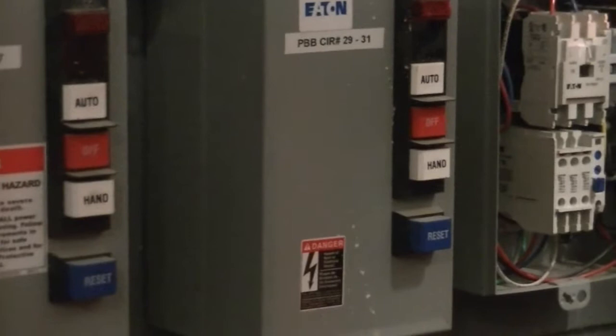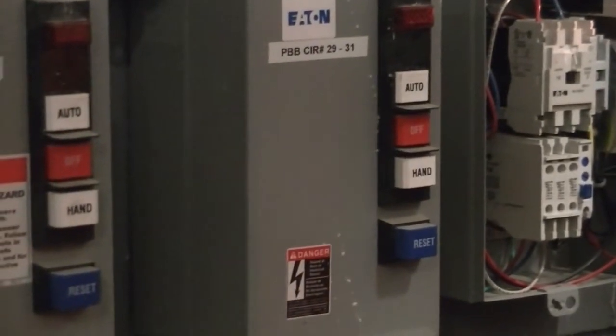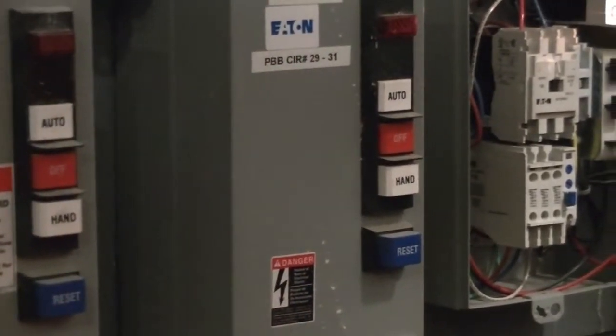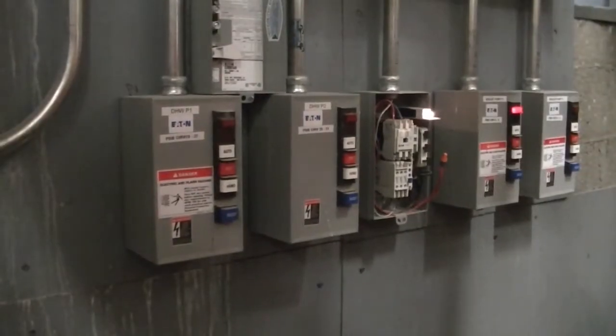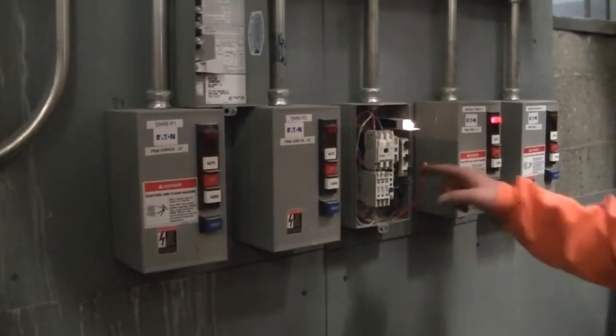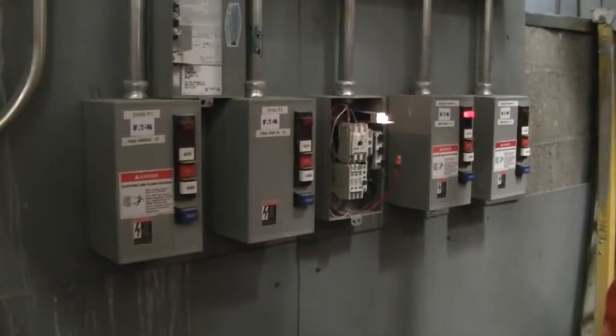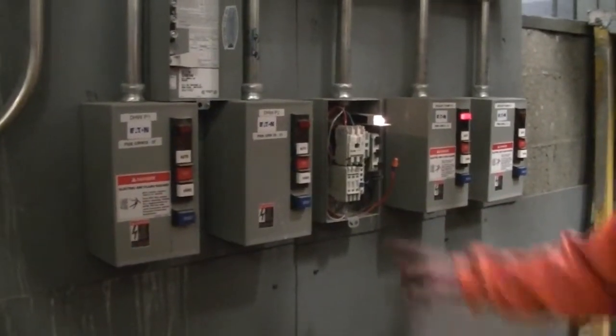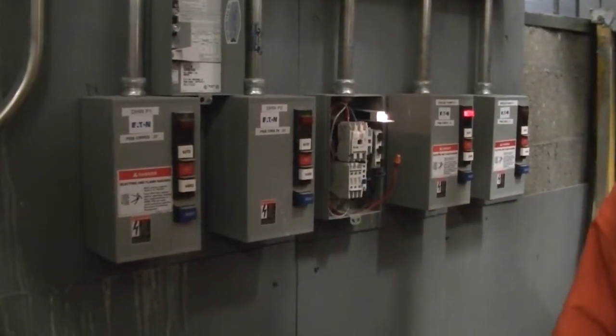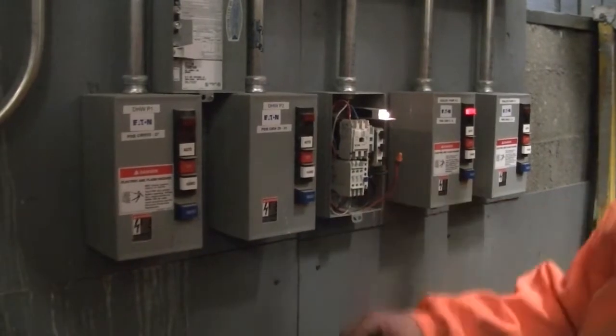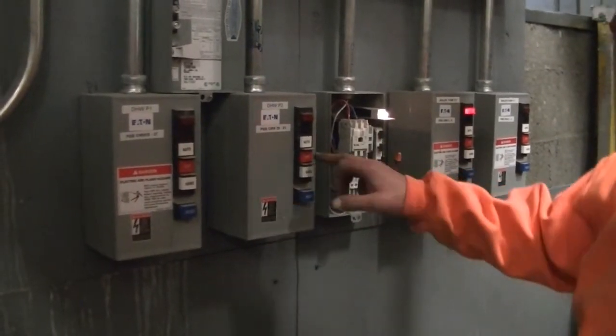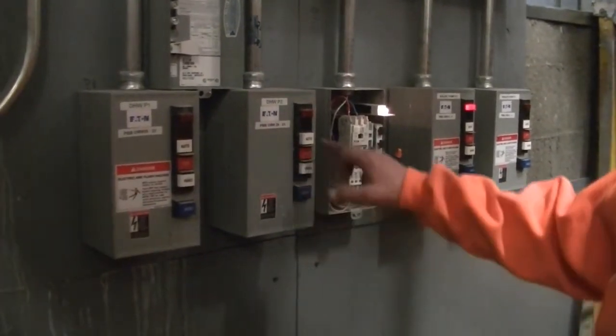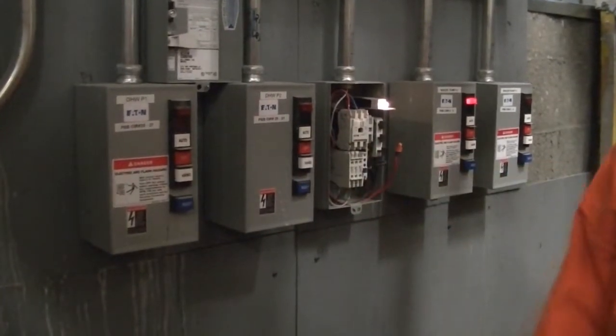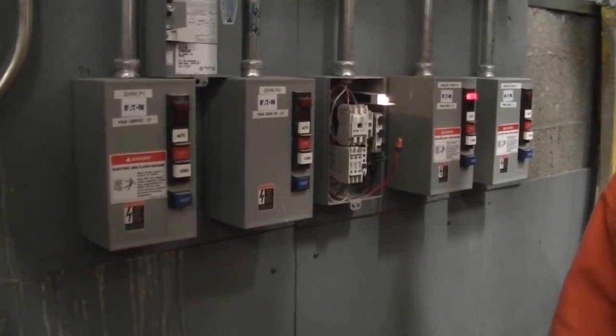Let's say the boiler's firing, and you come in and it's locked out on high temperature. First thing you're gonna check is to see if that pump's any good, okay? You hit the hand button, see if the pump starts. If the pump doesn't start, then the overload's probably tripped. You're gonna wanna reset the overload, pump in the off position, reset, return it to auto, reset your boiler, watch it fire up.